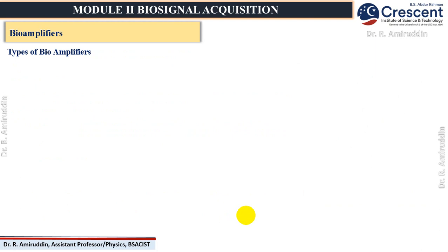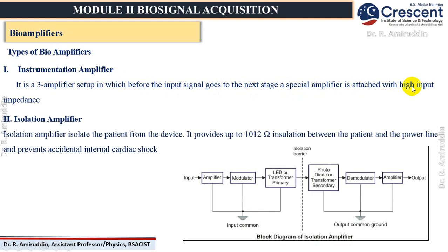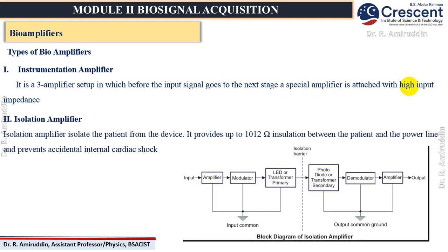There are two important types of bio-amplifiers. The first is the instrumentation amplifier — a three-amplifier setup in which, before the signal goes to the next stage, it comprises an additional specialized amplifier attached with high input impedance. The second is the isolation amplifier, which isolates the patient from the device. An isolation barrier is placed between the input signal stage and output signal stage, providing up to 10¹² ohm insulation between the patient and the power line, thereby preventing any kind of accidental shock to the patient.